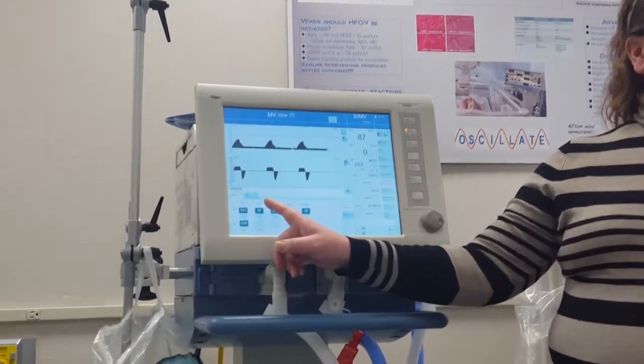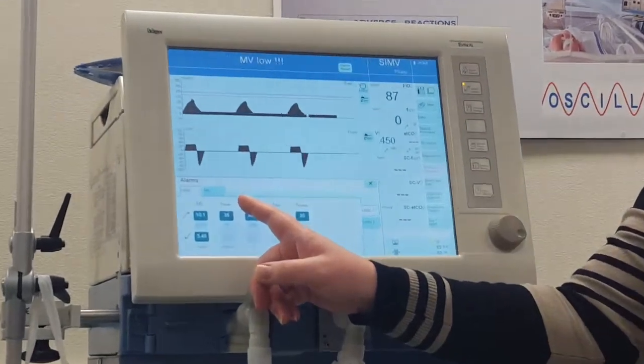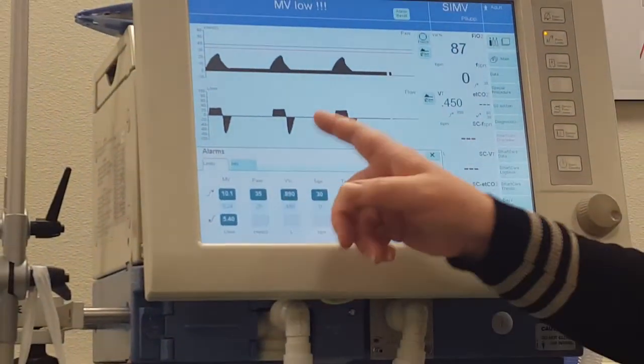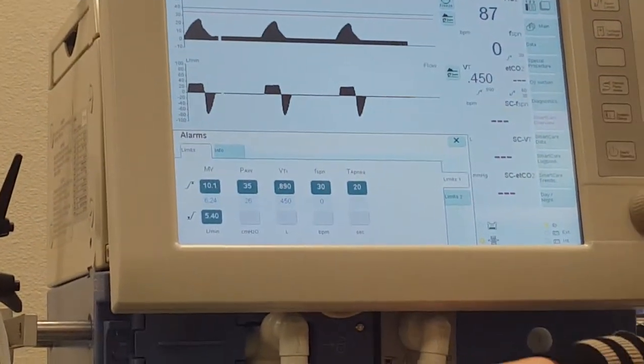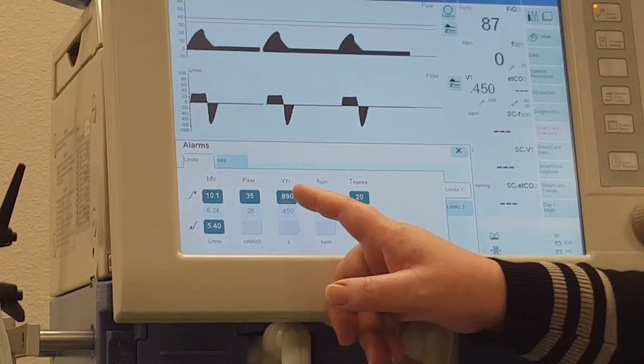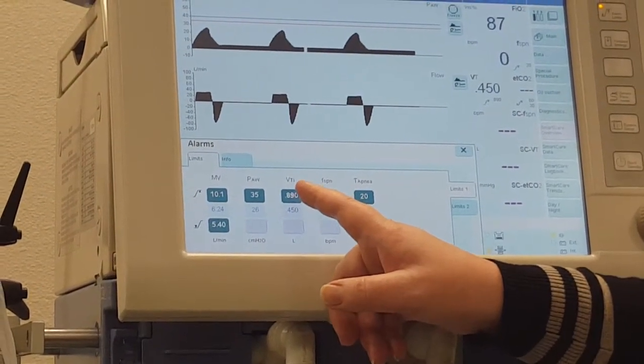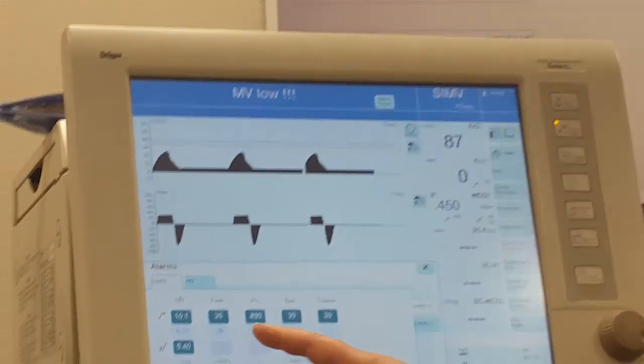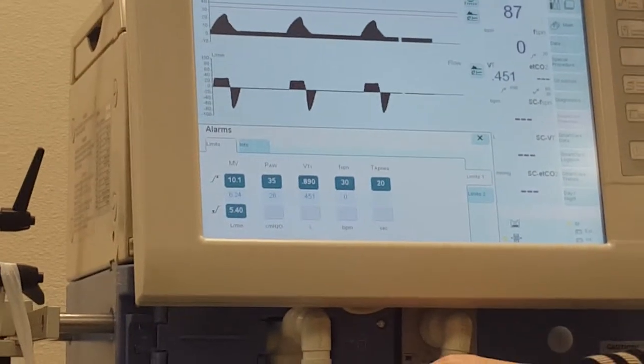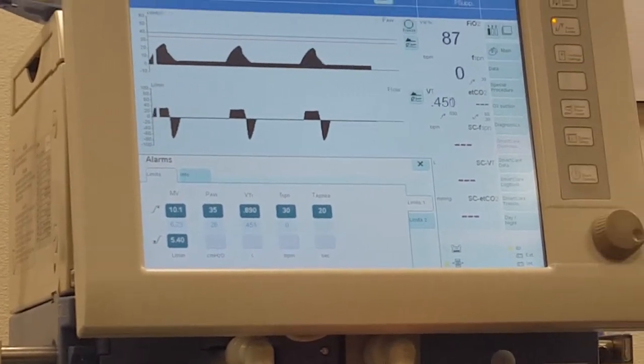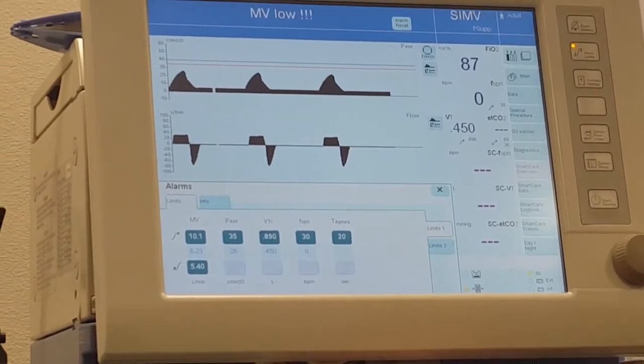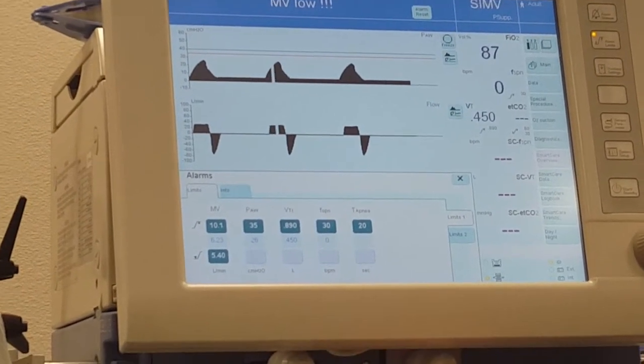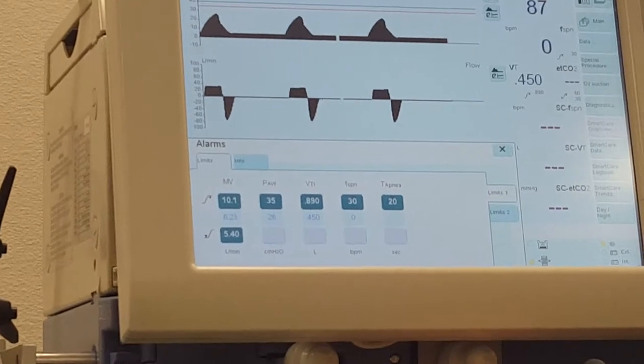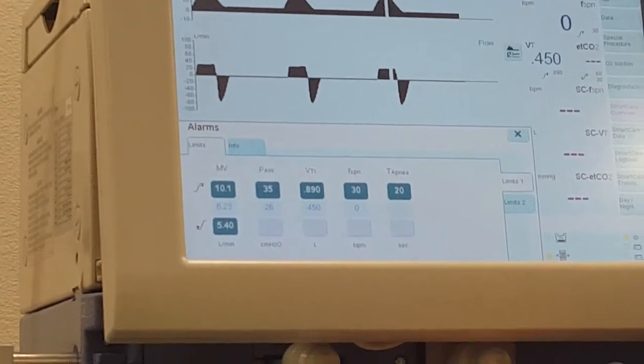PAW in the alarm section of the DRAGER stands for the high pressure limit, because you're going to learn where that needs to be set. Okay, VTI is your tidal volume. This is the one I told you was in liters. So remember, it's point whatever. So if you want your high tidal volume alarm to be at 700, it should say 0.700, not 7.00, which would be 7 liters. Huge difference.